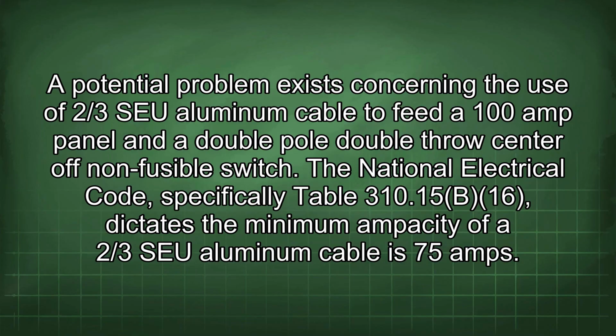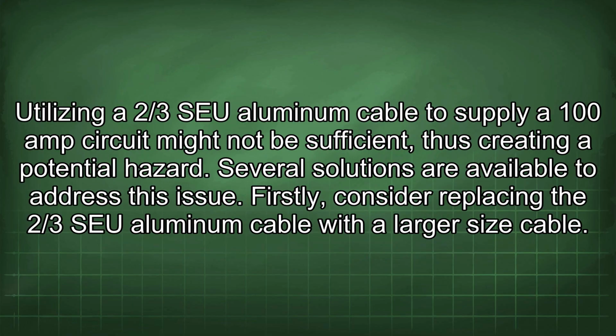A potential problem exists concerning the use of 2/3 SEU aluminum cable to feed a 100 amp panel and a double-pole double-throw center-off non-fusible switch. The National Electrical Code, specifically Table 310.15(B)(16), dictates the minimum ampacity of a 2/3 SEU aluminum cable is 75 amps. Utilizing a 2/3 SEU aluminum cable to supply a 100 amp circuit might not be sufficient, thus creating a potential hazard. Several solutions are available to address this issue.